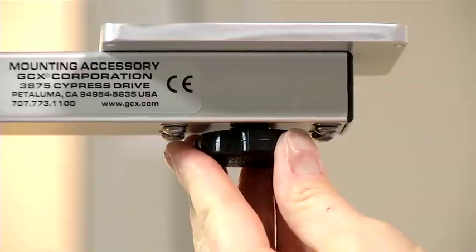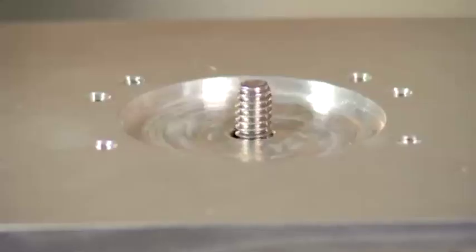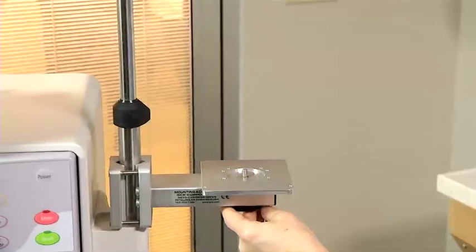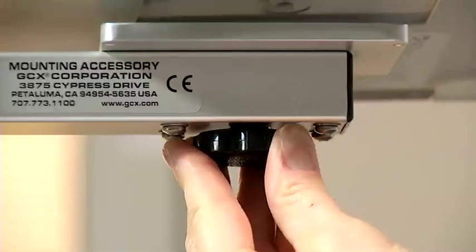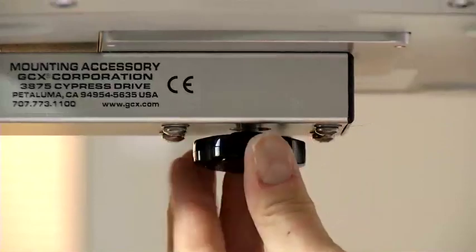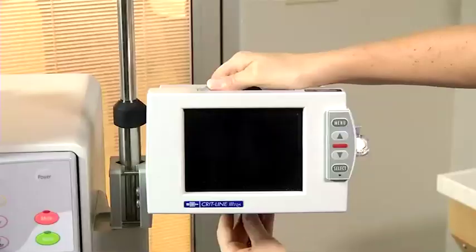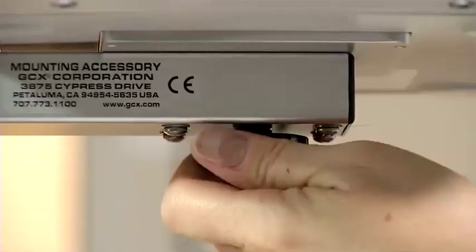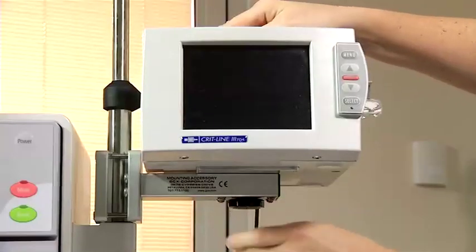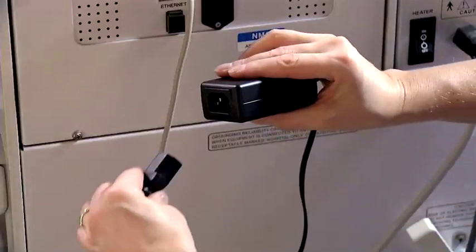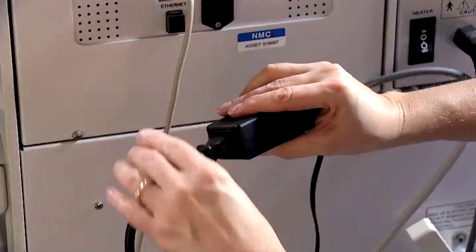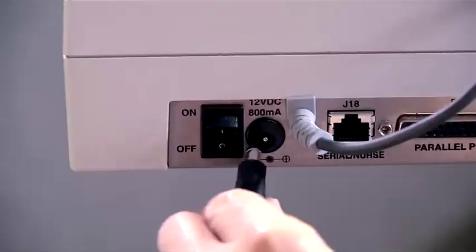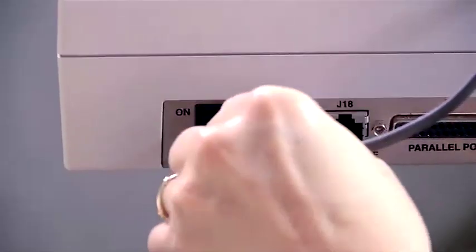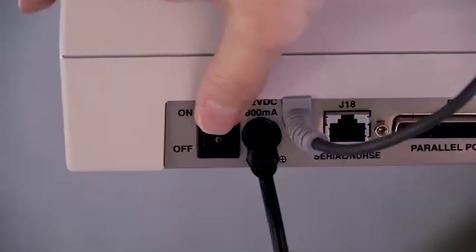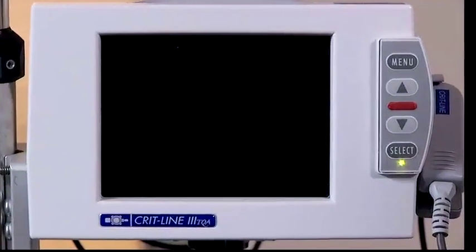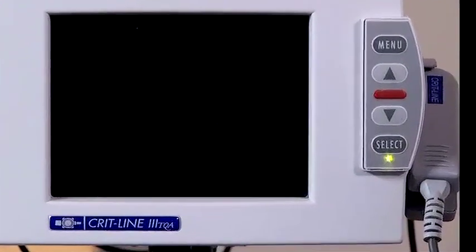Insert large black cap screw up from the bottom of the pole mount. Position the CritLine monitor on top of the screw so it lines up in the circle area on top. Tighten the large black screw by turning from below until monitor is secure. Connect the universal power supply cords together and attach to the back of the monitor. Turn power button on. The green charging indicator light on the bottom of the button pad should illuminate.